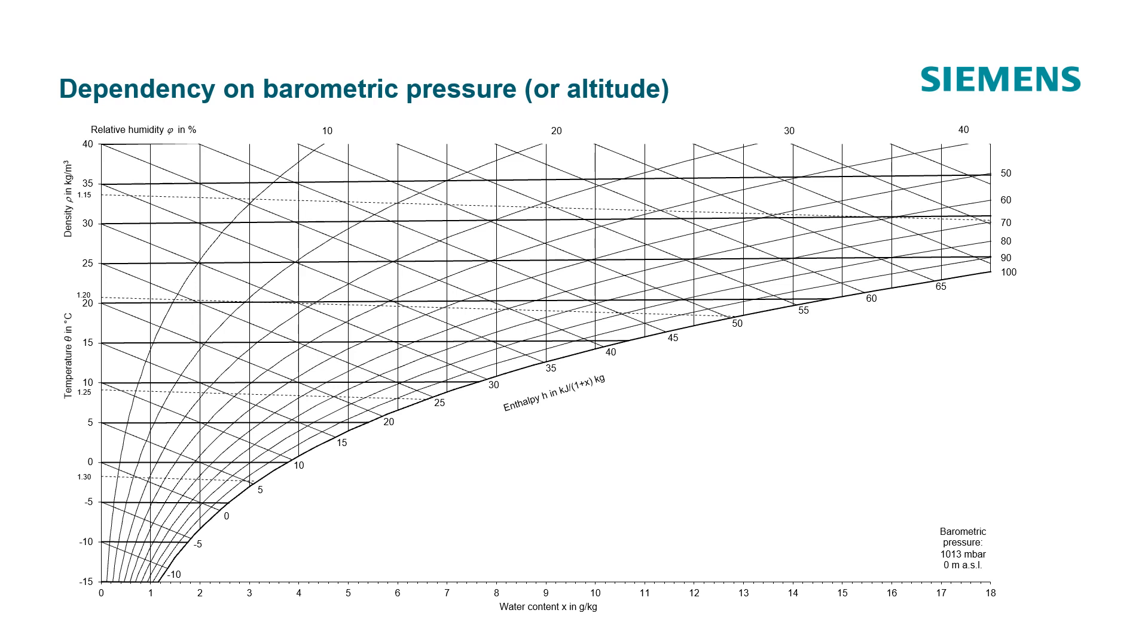Dependency on barometric pressure: The behavior of humid air is strongly dependent on the prevailing barometric pressure, respectively on the altitude. Therefore the indication of the used barometric pressure, respectively the altitude is essential. The diagram shown is defined for a barometric pressure of 1013 millibar, which corresponds to an average barometric pressure at sea level.